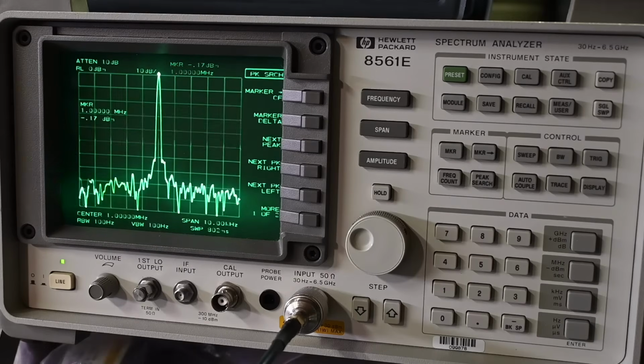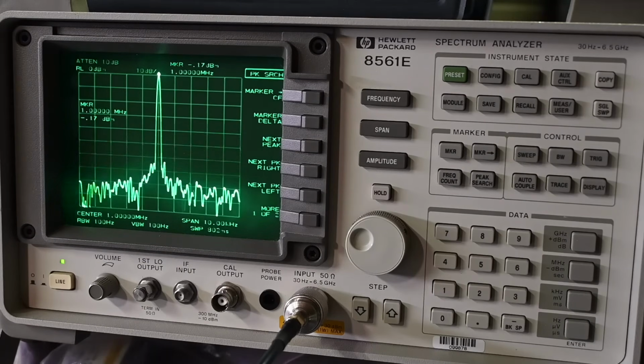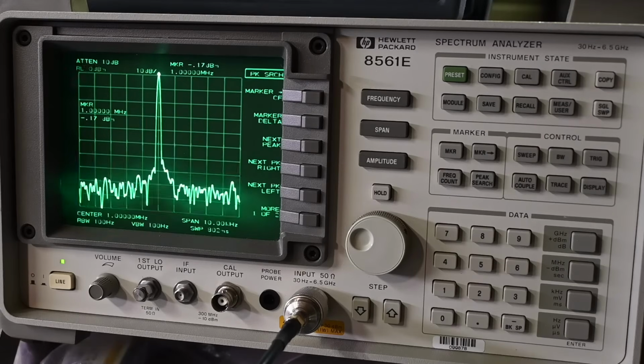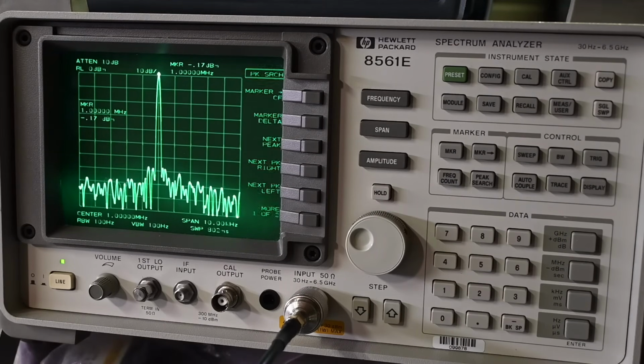Now, keep in mind that for actually testing the RF output amplitude on the signal generator, you don't want to use a spectrum analyzer to check the actual calibration and see if it's within spec. You need to use a power meter and have the power sensor right on the RF connector on the signal generator, because there's some very measurable loss in the RF cable between the spectrum analyzer and the signal generator, and you don't know exactly how much loss, so that's kind of an unknown. So you really can't rely on this value for the amplitude as an actual measured amount. You wouldn't want to try and calibrate using that or something like that.